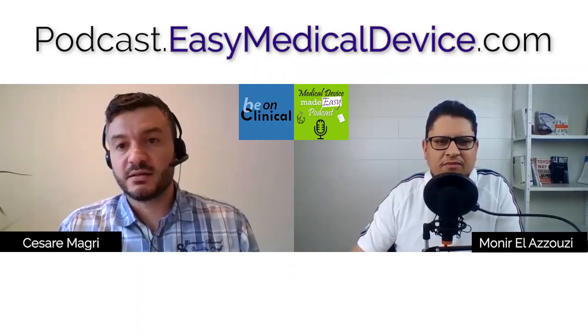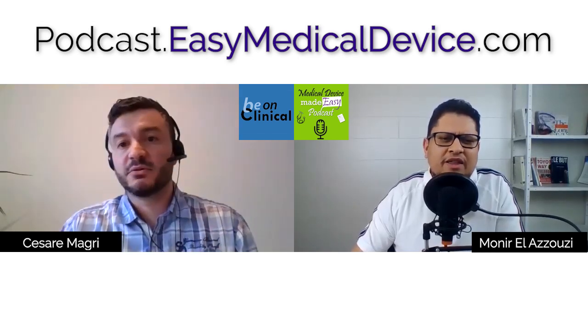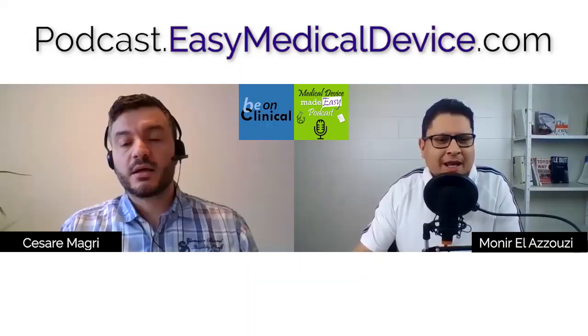And here we usually have a sub point which is called contraindication, which is also very, very important, because it's where you remove all the conditions that you don't want to deal with with your product. So I think it is also important to have those contraindications in terms of clinical, to say that we have not tested that on those people, or we don't recommend to test that because we have no proof that it's working on those people. So having that is making it clear for everybody to be careful. This is maybe working. I'm not saying it's not working. It's just that I don't have true data about that.